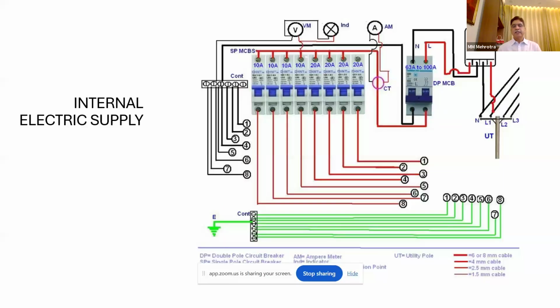Now I am showing you a wiring diagram of a single phase system. Here it is, 8 circuits. Supply is coming from outside, the SEB. It goes to my metering system and comes to my main switch. Now the main switch is connected to this distribution board. Red is your phase, black is your neutral, and green is your earth wire. So neutral and earth wire color will always be the same, black and green. The phase wire will be different, red, yellow and blue, depending upon the phase which we are using.